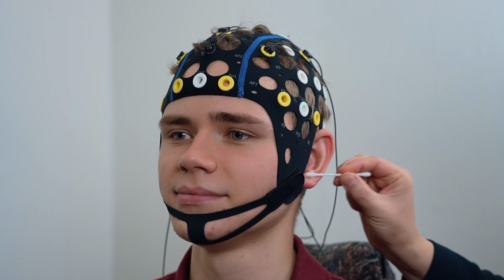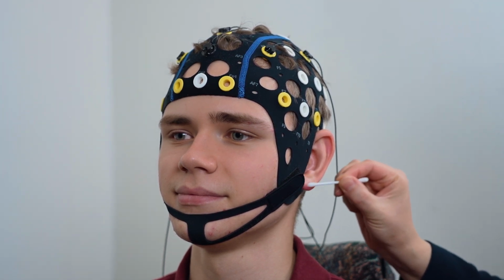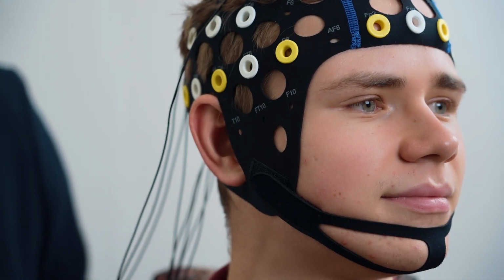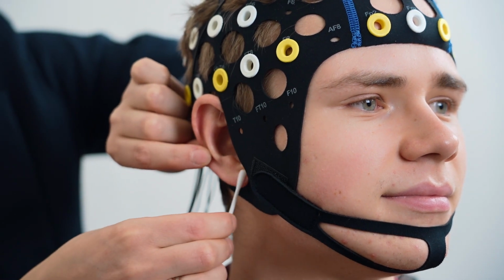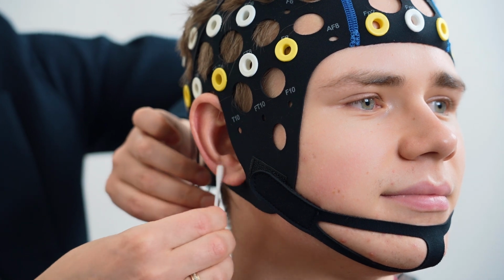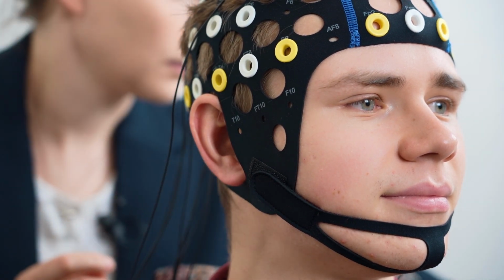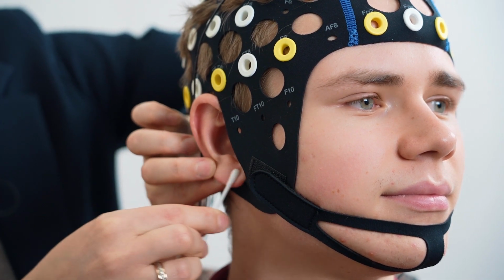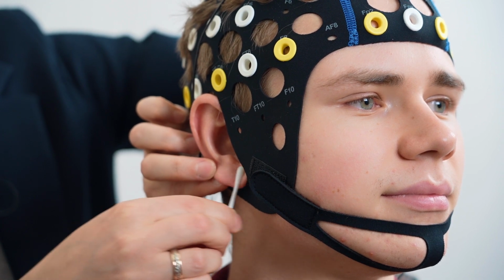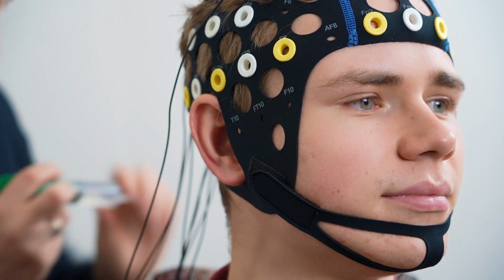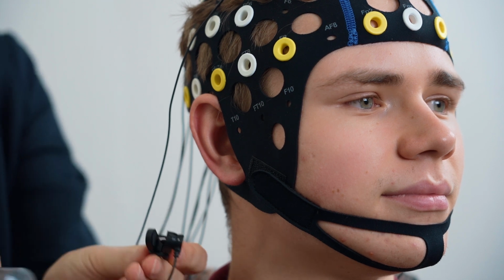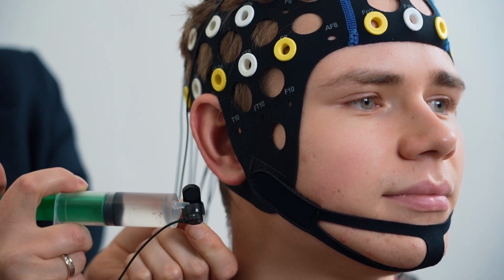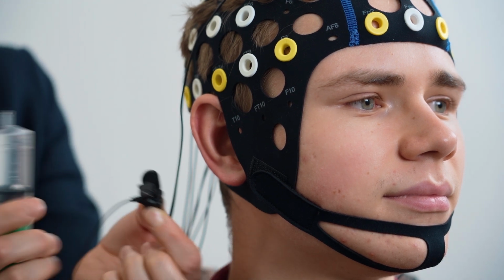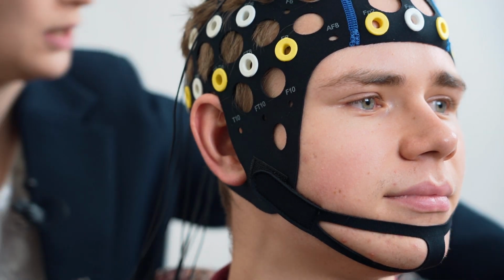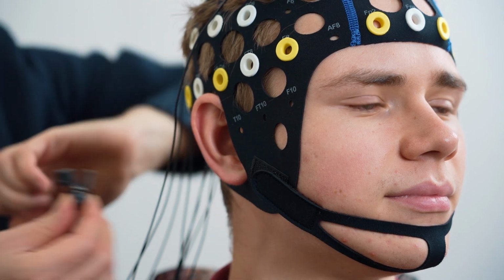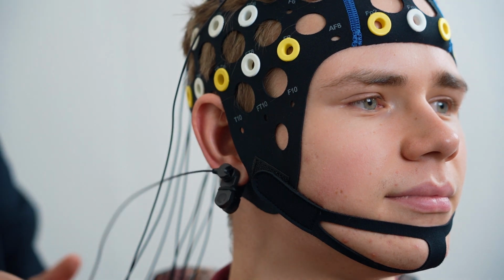When installing reference ear electrodes, we perform all the same operations. Now we install the second ear electrode on the right side, A2. Degrease the skin with alcohol. Treat it with a scrub. Add gel to the electrode surface and fix it with a clip to the earlobe. Then we connect it to the amplifier.